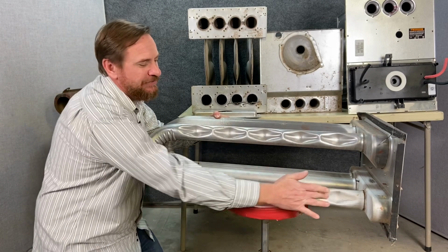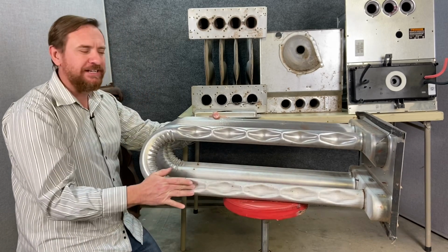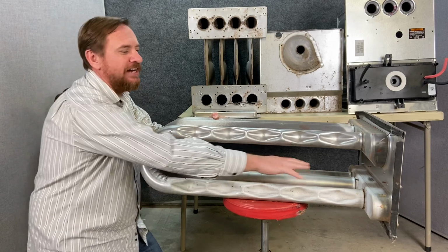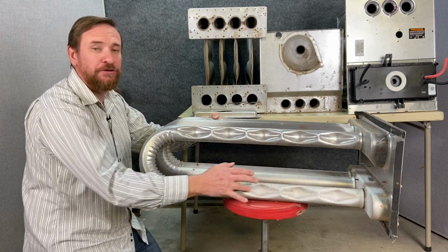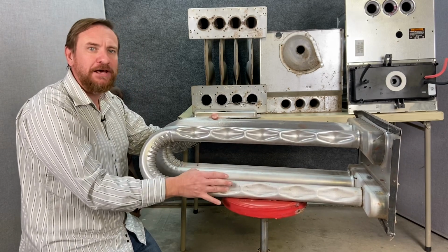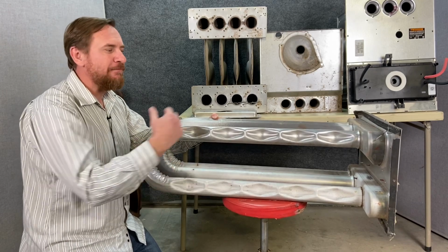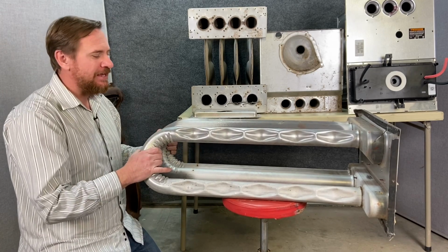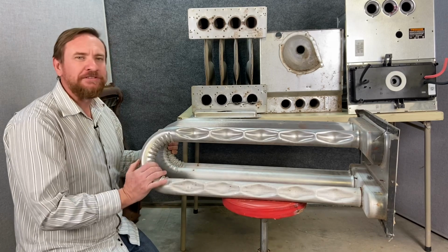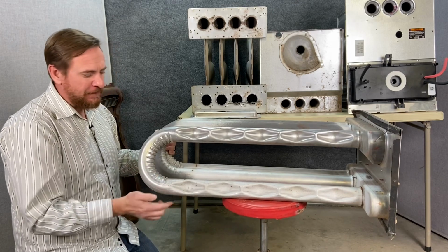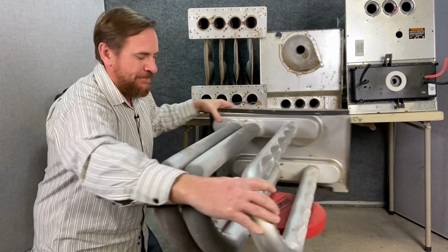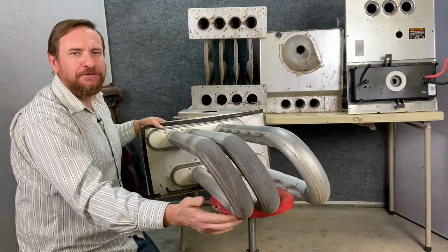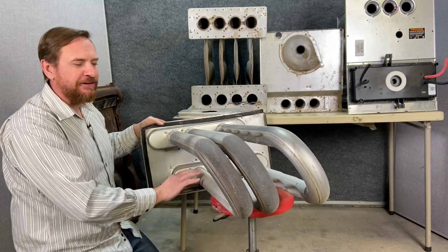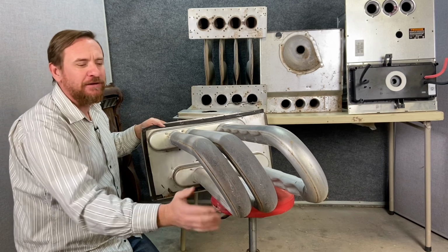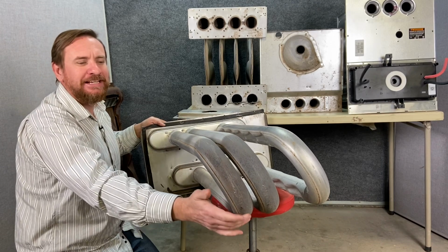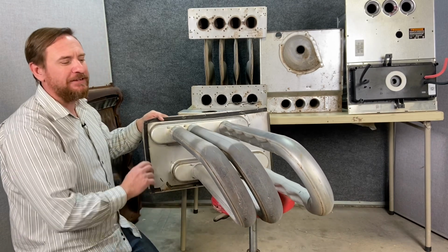And what happens, if you see, this pipe has all these grooves in it. The idea was that these hot gases were actually put through, second law of thermodynamics, more metal, more surface area, so we can get more heat out of this appliance. Now, notoriously, these tube style heat exchangers would fail, especially right here at these end tubes. The main cause of that was overfiring. Somebody wouldn't have the gas pressure set correctly, and the flame would actually burn against the end, and it would cause them to burn out.